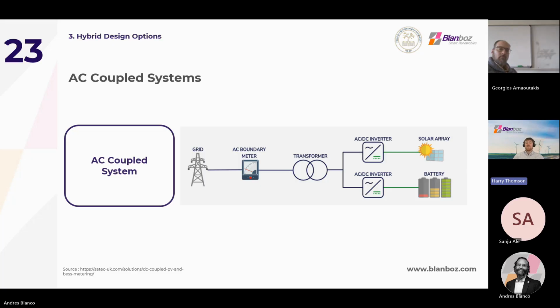So the primary advantage with this is that it allows operators to stack grid services, maximize revenue streams, and potential profit. This can be paid for services that stabilize the grid and can be paid on availability, so just being available, or for utilization, actually using the battery. As the PCS are different for the BESS and solar, you also have more options for procuring the battery PCS. This allows for different and or more custom setups where you can tailor the equipment to your project's needs, especially for augmentation when you're adding capacity down the line.